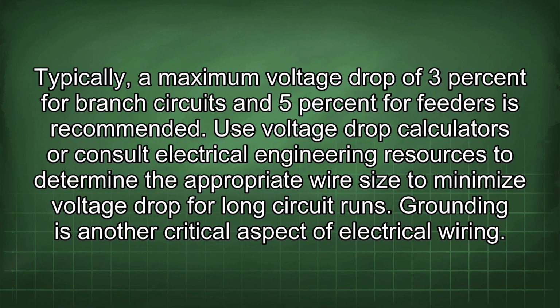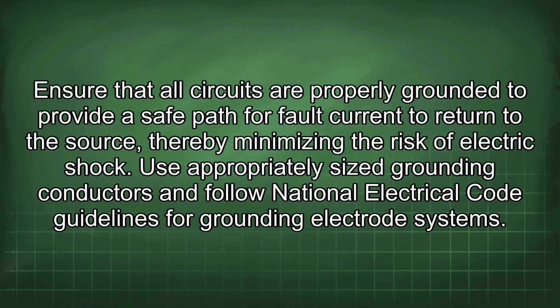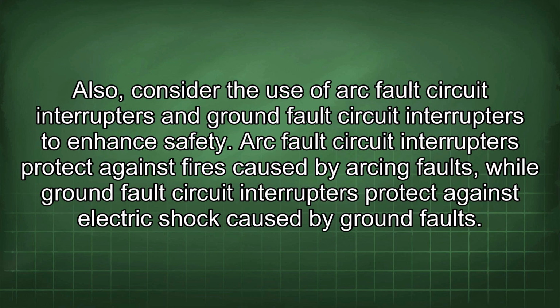long circuit runs. Grounding is another critical aspect of electrical wiring. Ensure that all circuits are properly grounded to provide a safe path for fault current to return to the source, thereby minimizing the risk of electric shock. Use appropriately sized grounding conductors and follow National Electrical Code guidelines for grounding electrode systems. Also, consider the use of arc fault circuit interrupters and ground fault circuit interrupters to enhance safety.